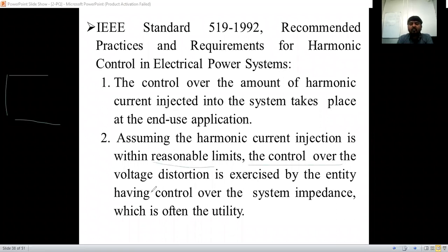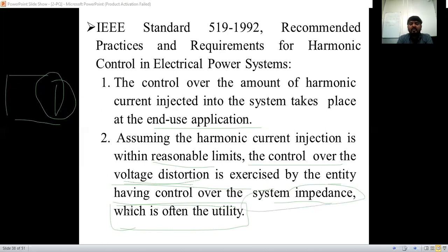The control over the voltage distortion is exercised by, we have to exercise a voltage control, that is called voltage distortion control. We can exercise it by the entity having control over the system impedance. By controlling the system impedance, we can control the voltage distortion, which is often done on the utility side. The current is something we can control at the end use application, and by using the utility side, by controlling the system impedance, we can control the voltage distortion.